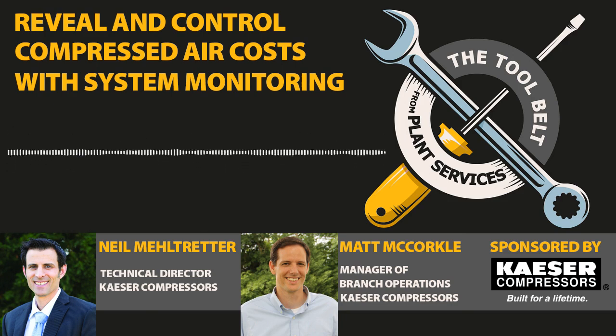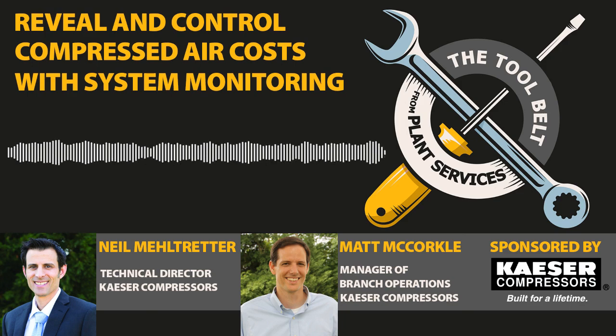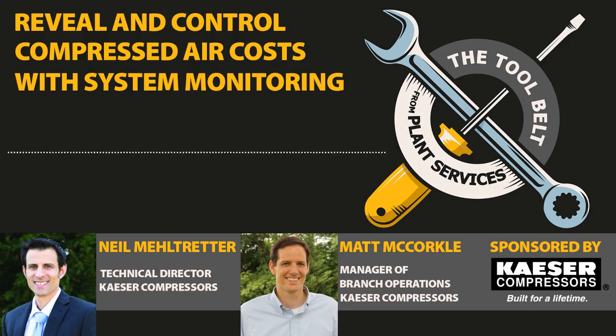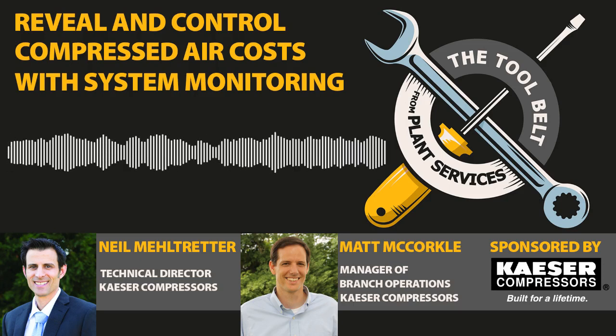And then in terms of air quality, so your pressures, that you haven't had any minimum pressure events, and that your air treatment is all operating as designed. So you're not getting additional moisture or oily condensate down in the line, causing potential rework or scrap. So those are really, I think, the most real-time monitoring things that are most critical to reducing hidden costs to an absolute minimum.